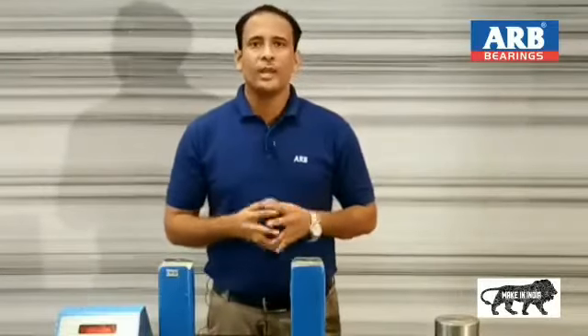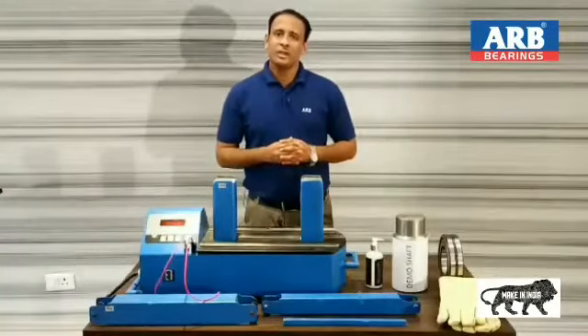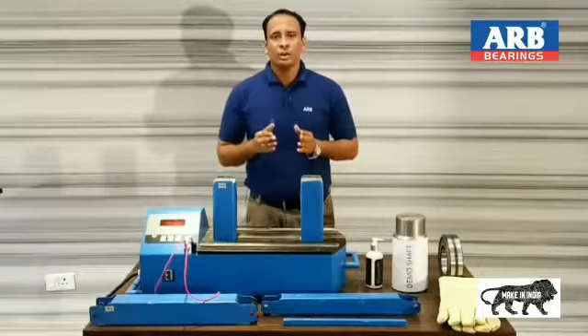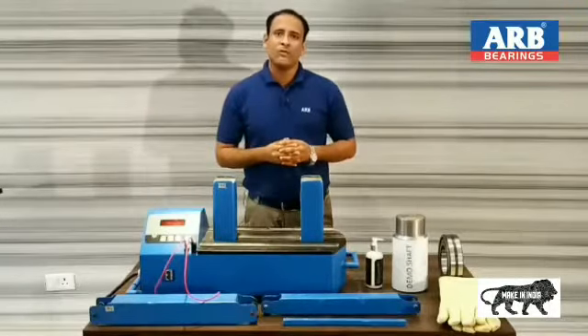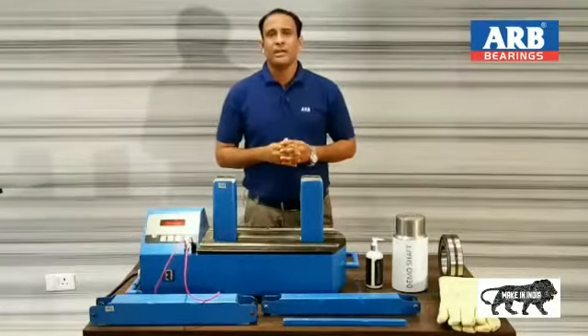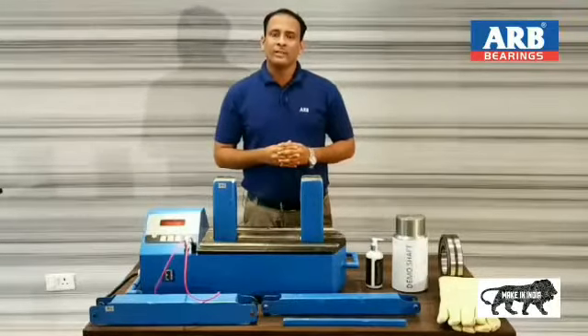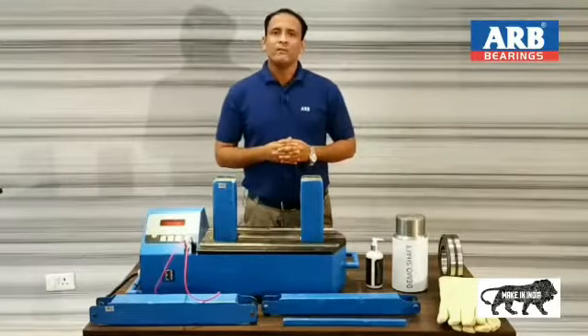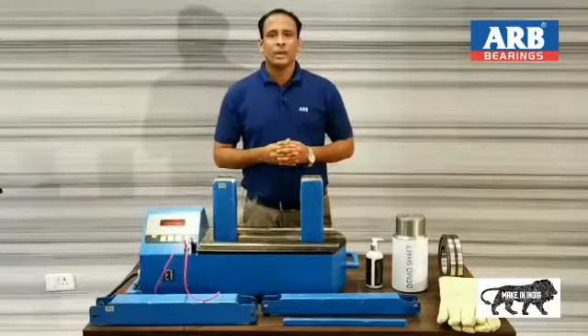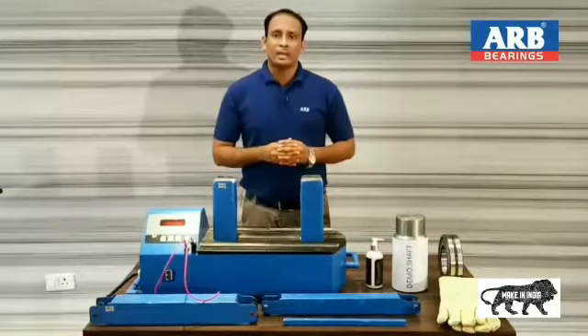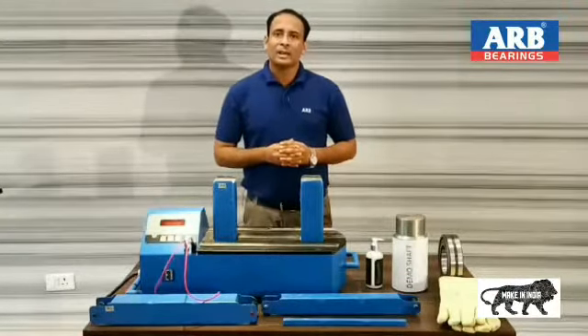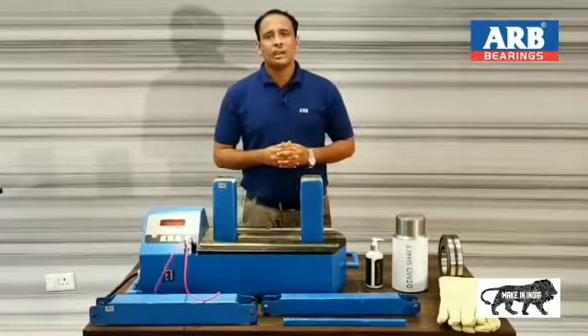Few more things I want to tell you. ARB bearing heater is designed in a manner that these heaters can cover a large range of bearings within a single unit, and you need not buy different units for different bearing sizes. ARB bearing heater has a special demagnetization feature which performs demagnetization on the bearing after heating, as a magnetized bearing may cause damage to its life.